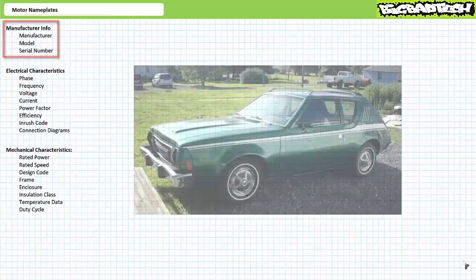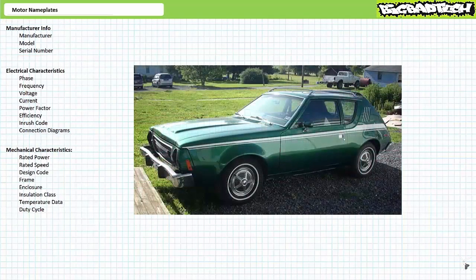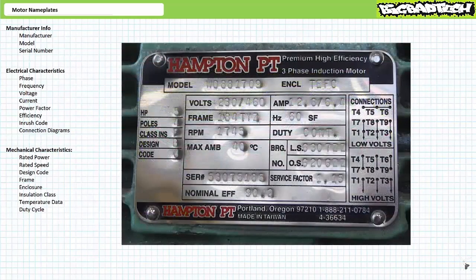Let's take a look at the manufacturer information category first. Manufacturer, model, and serial number. This basic information is comparable to the make, model, and VIN number of a car. The manufacturer is the company that made the motor. The model number, or sometimes catalog number, is specific to that manufacturer. It means only something to them and not any other manufacturer of similar motors. The model number is that manufacturer's means of coding that specific style of motor, and it is also useful for finding replacement parts for that specific style of motor from that specific manufacturer.